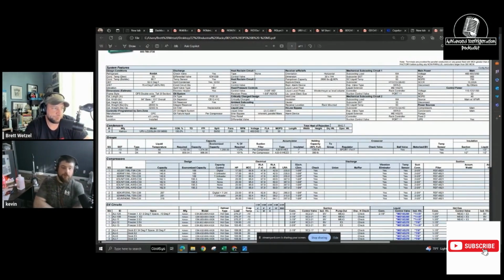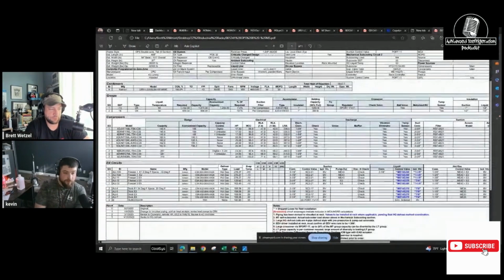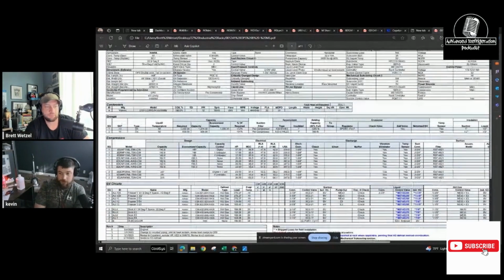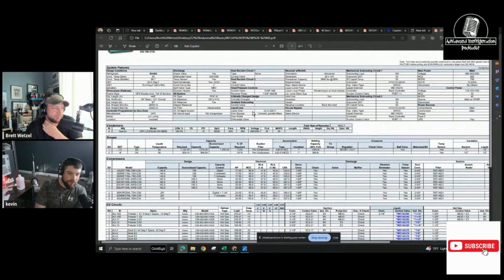Yeah, making sure that the condenser is clean, spotless, especially if you're walking into a rack and you're a newer guy. If you're there on a Friday, just clean the condenser. Don't screw the guy for the weekend. What do you mean? Yeah. Stop it. You would go ballistic at that. I know, ballistic. But yeah, it's looking over the schedules and finding your TDs and stuff like that, and just tracing out your main circuits and seeing how everything's laid out.